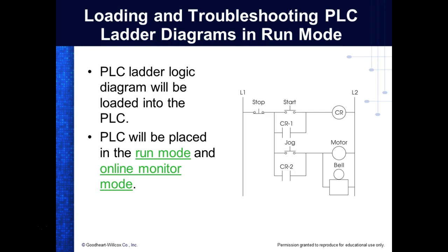So normally we write our programs offline, right? You understand? So we switch our program to offline. Everybody see how to do that? Are you okay there? And then all we have to do is download it. Now the problem if you've got one of the 504s, you're going to have to remember to take that key. If you don't have it in remote, you're going to have to remember to switch it from run to the program. Everybody okay? If you put it in the remote, it'll work just like this, but it's up to you.